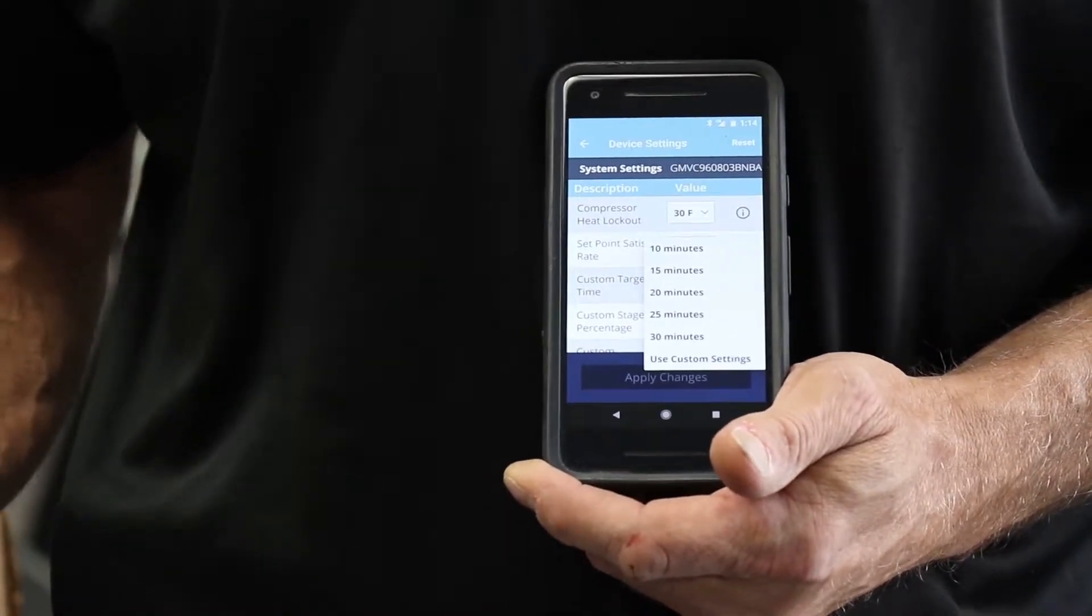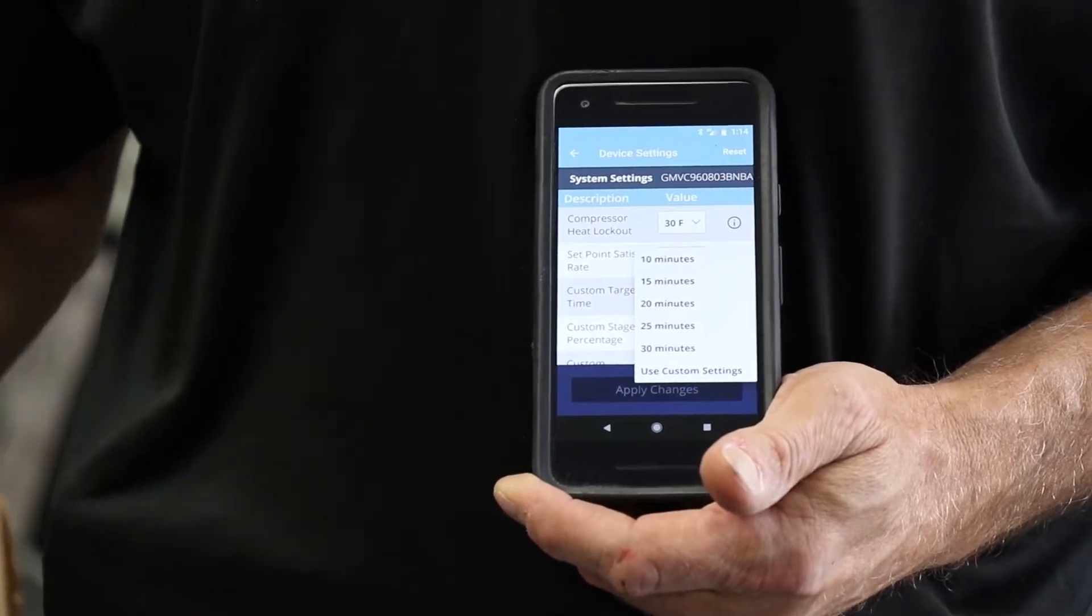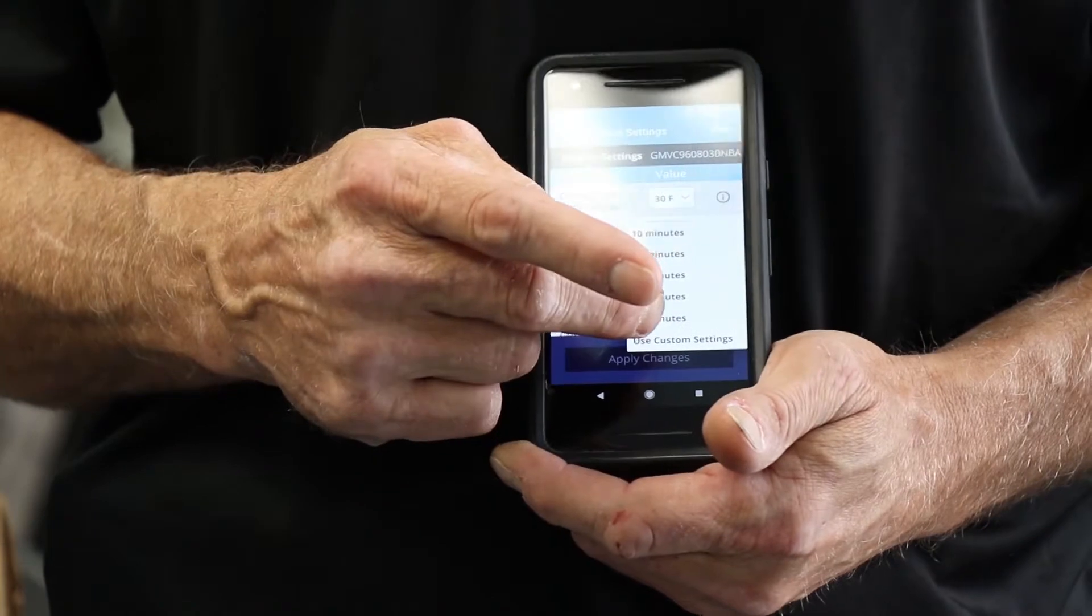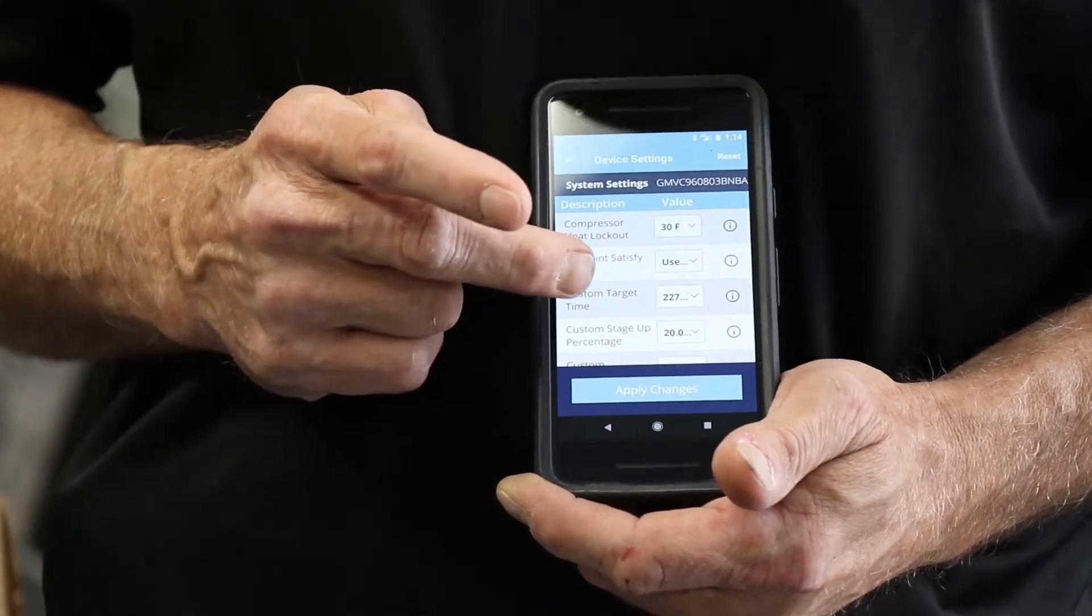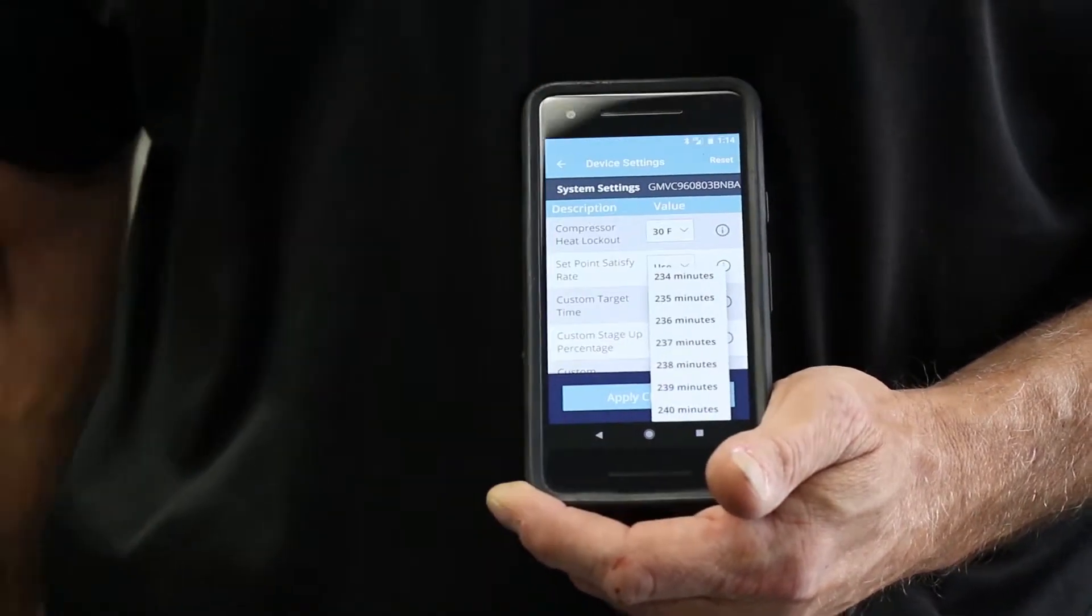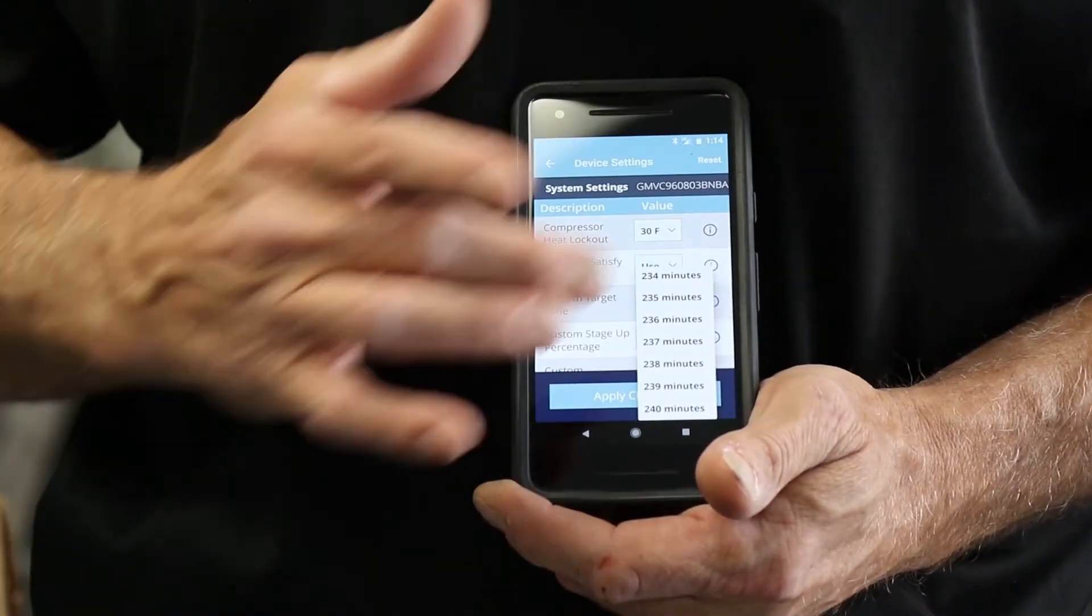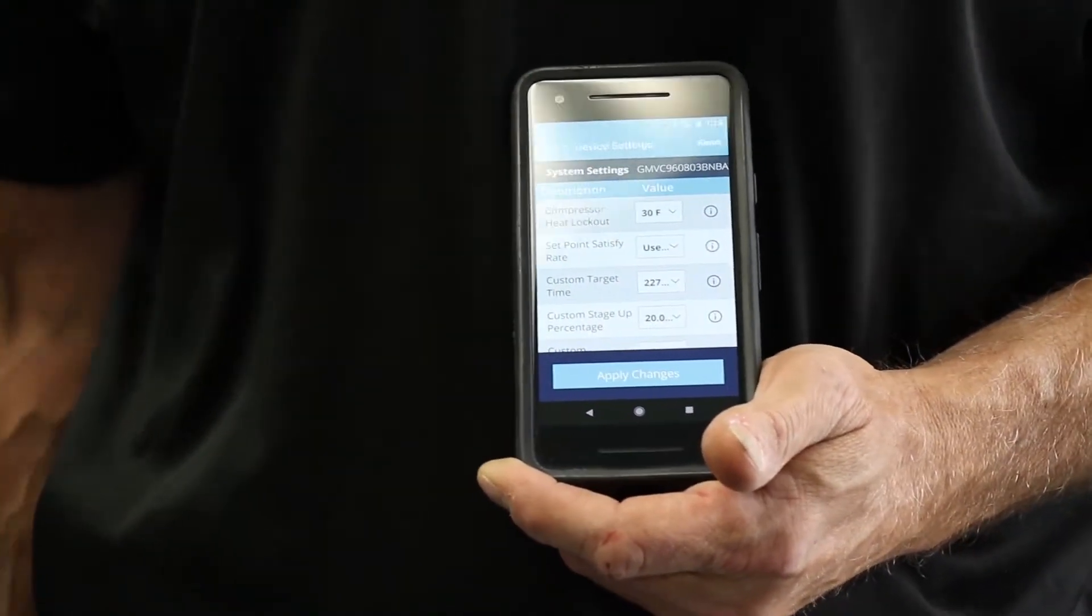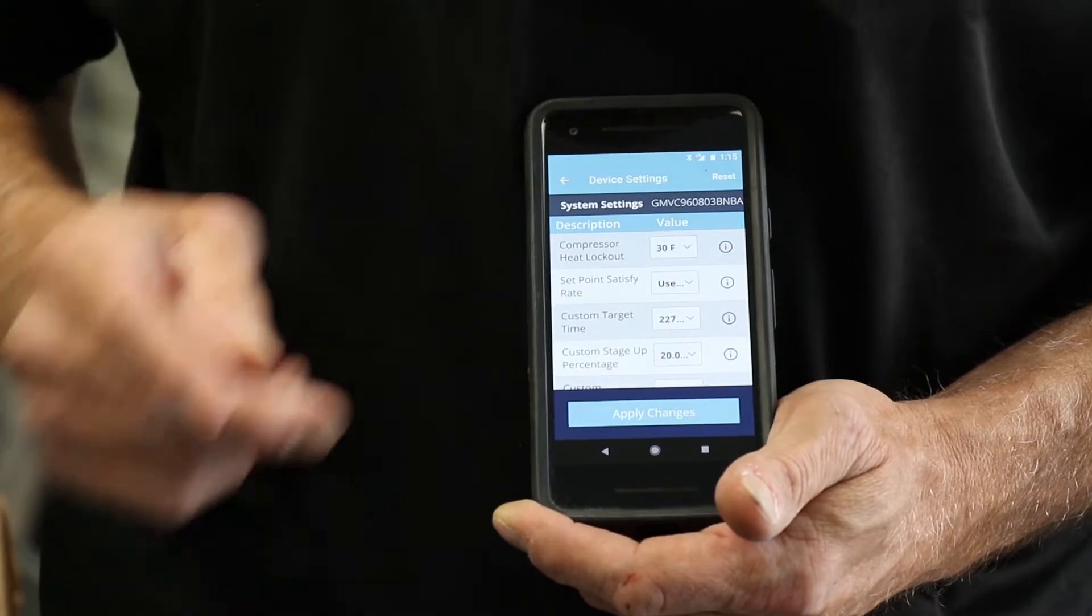So we may keep a longer first stage before we go into high stage or vice versa. If we use a custom setting, now we can change our staging all the way up to 240 minutes before we go into high fire or all the way down to one minute if we want to eliminate the staging and go right to high fire.